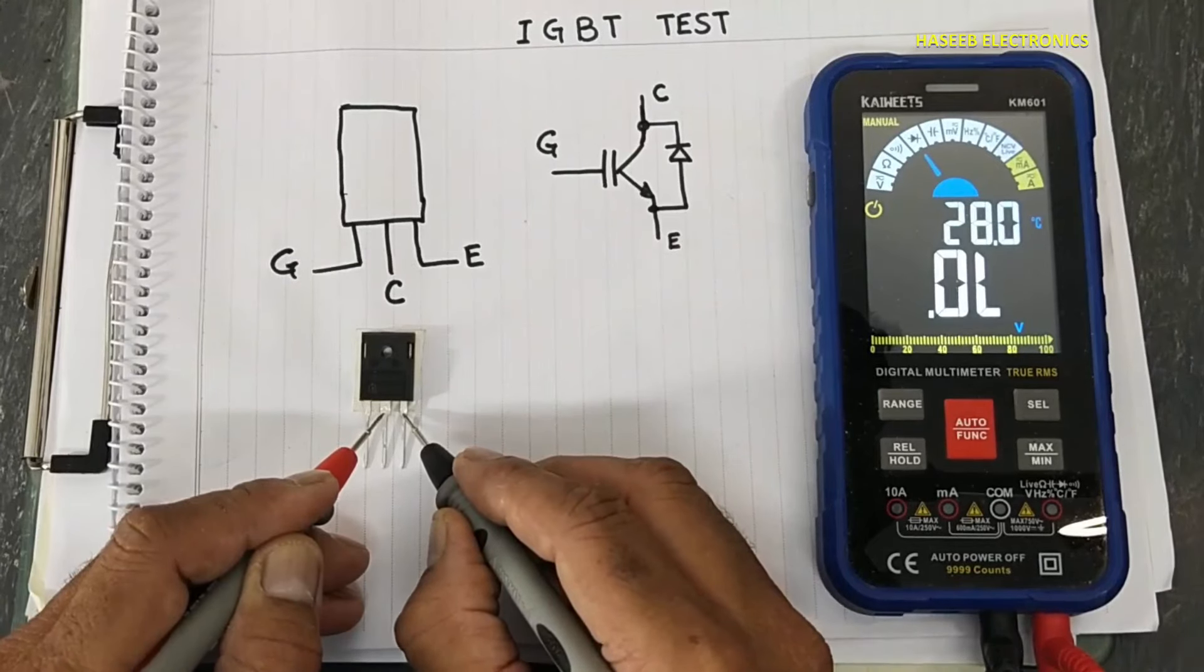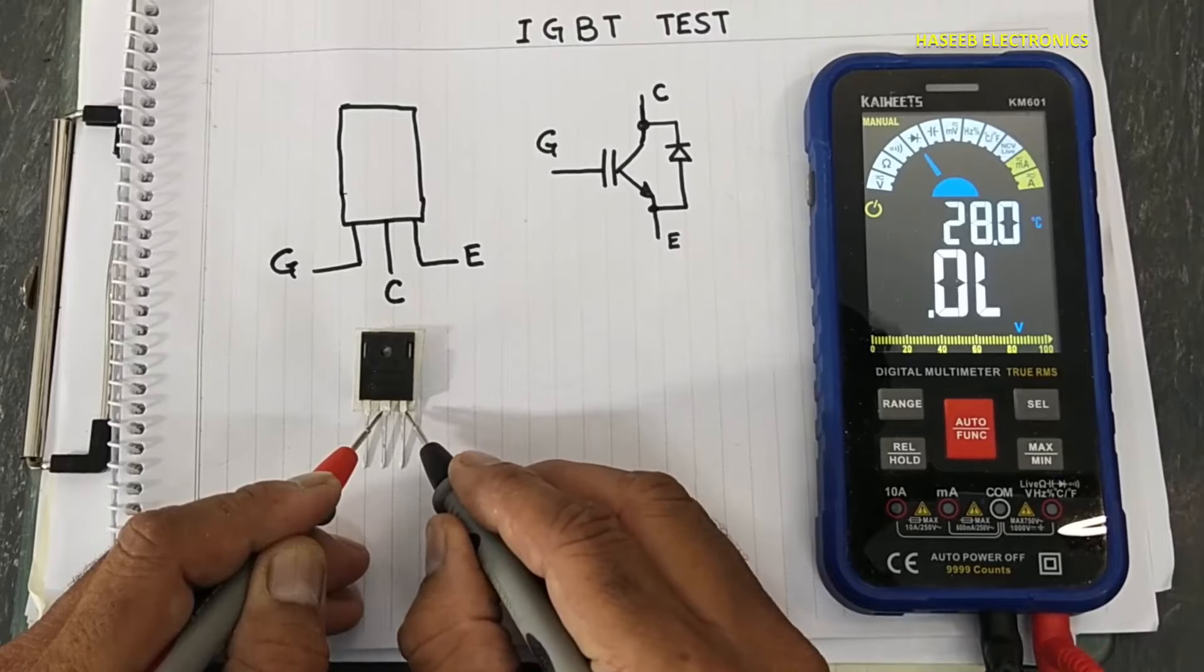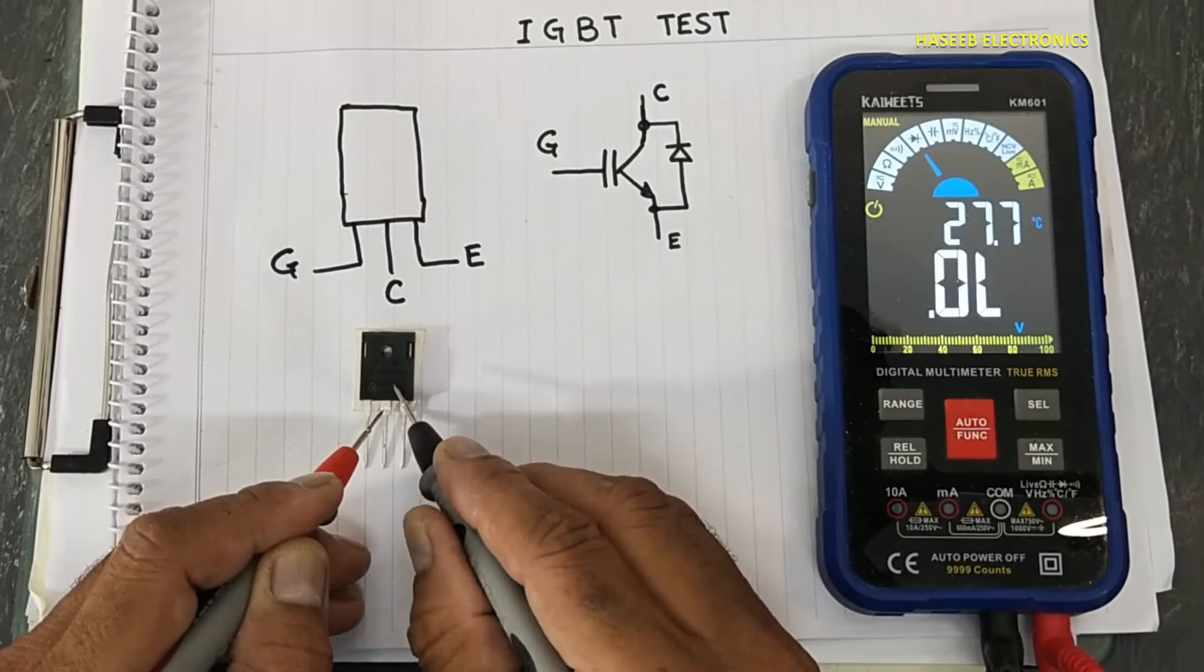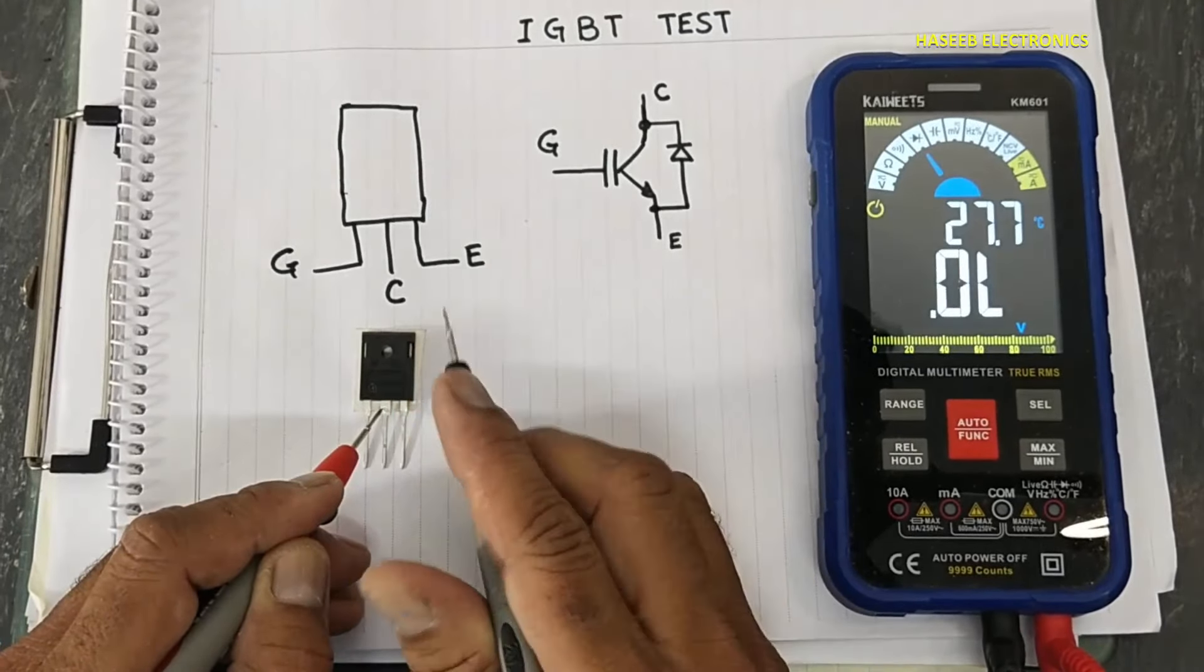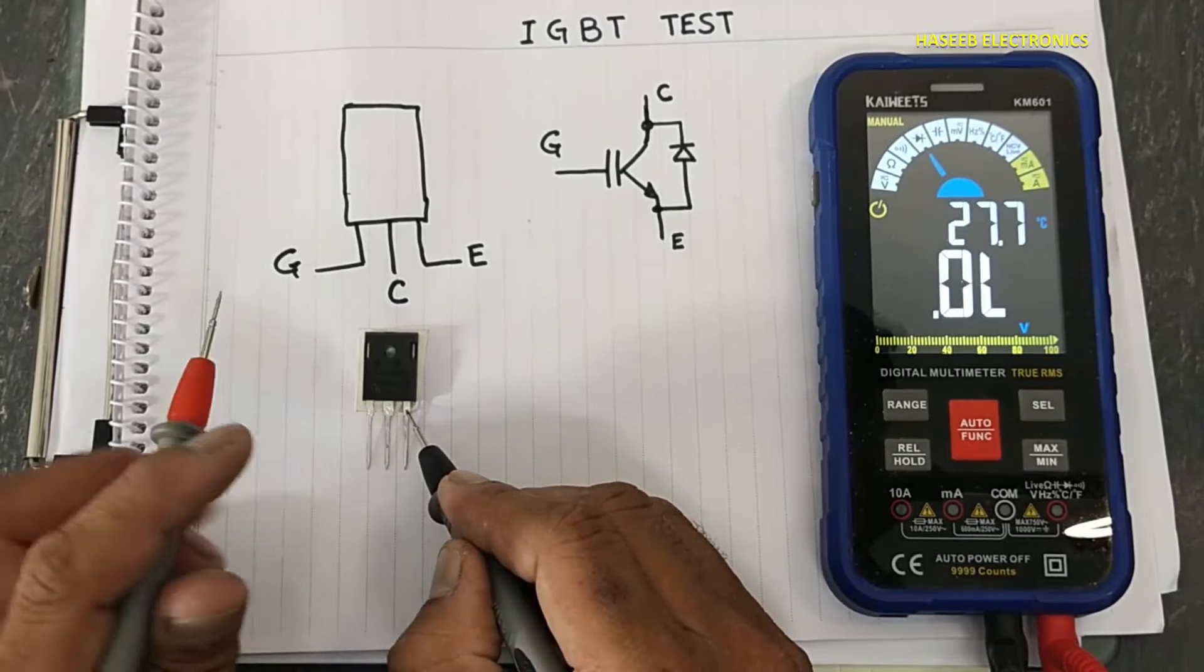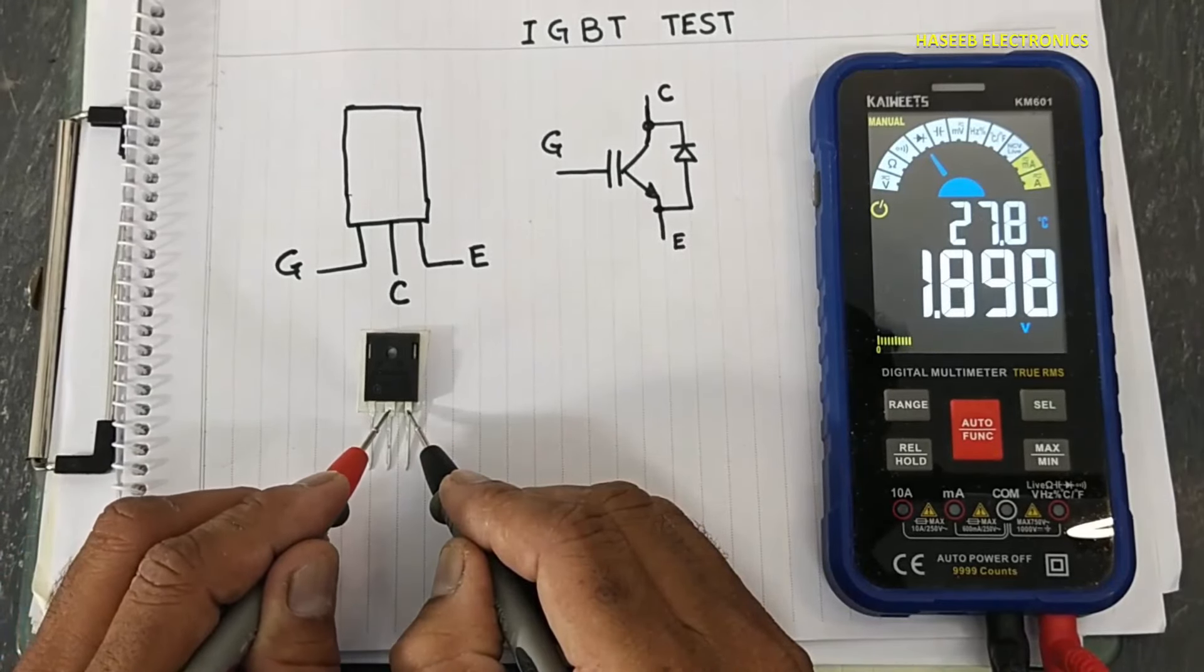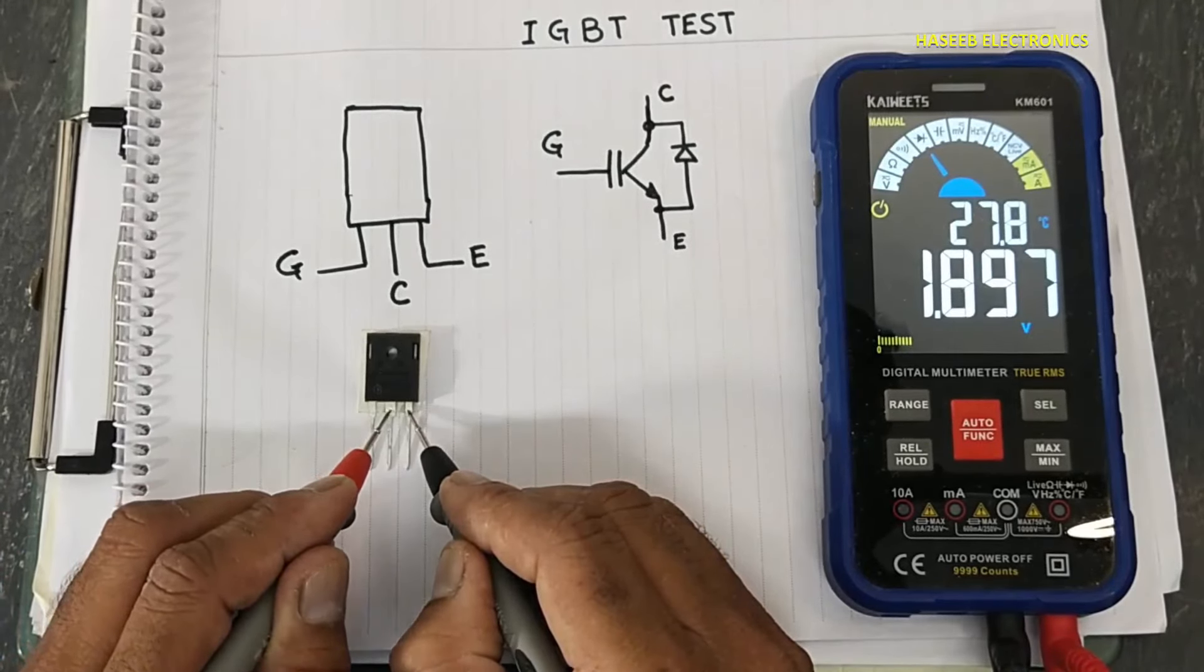If it is giving short circuit here, that time IGBT must be replaced. If we charge the gate like this - black lead at emitter, red at gate - and check here, if it is not turning on, that IGBT is bad.